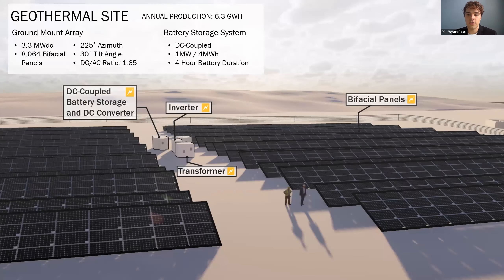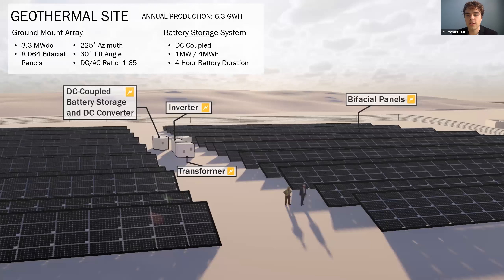With this strategy in mind, as well as other university goals, we arrived at our final proposal. A 3.3-megawatt ground-mount PV array with a 225-degree azimuth and a 30-degree tilt angle, along with a 1-megawatt, 4-megawatt-hour DC-coupled battery storage system, was designed at the geothermal site. This array is a fixed-tilt array consisting of 8,064 bifacial panels. Due to light-colored soil in the region, bifacial panels were selected to increase production early in the day when the panels are not directly facing the sun. This contributes to low-light harvesting for charging the battery system and has the potential to increase total production by 9% annually. Combined with the array's orientation, these design choices minimize operational costs and maximize production during NMSU's on-peak period. The DC-coupled battery system was selected based on several factors, including lower balance-of-system costs and the ability to charge from clipping recapture, which guarantees the project can monetize 100% of federal tax credits.